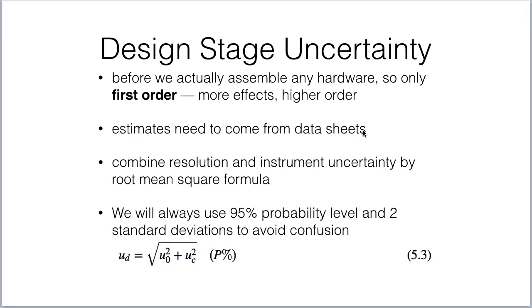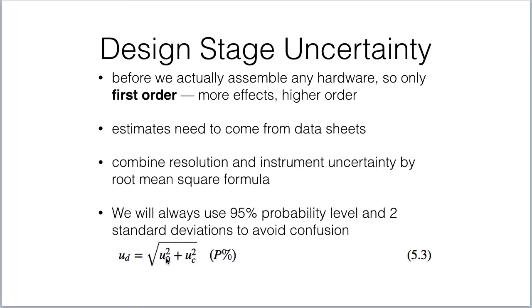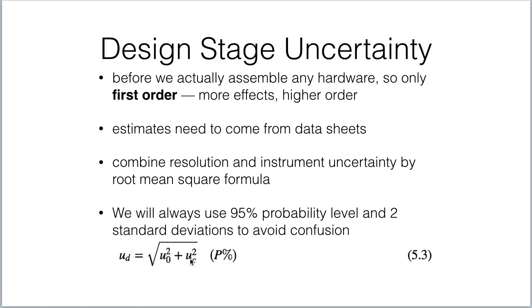Our estimates at design stage come from data sheets because we don't have any hardware yet, and we'll have manufacturer's uncertainty from those data sheets. We combine the resolution and the instrument uncertainty using the root mean square formula, always at 95% probability and two standard deviations. So our design stage uncertainty is the square root of the zero-order resolution uncertainty squared plus the instrument uncertainty squared.